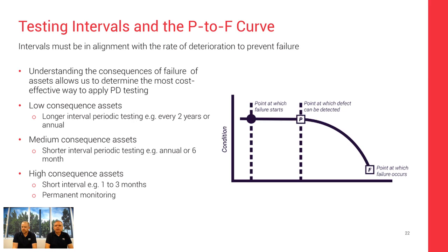When I first started doing this, when EA Technology started really pushing the use of this into the electricity industry in the UK back in the 80s and 90s, we started looking at maybe every 2 years as a good starting point. One of the reasons for that is we were looking at very much void type problems: compound insulated cable boxes, compound insulated chambers and oil filled switchgear. And if you're looking at a void degrading through bitumen and things like that, it's usually quite a long process before it goes into failure.